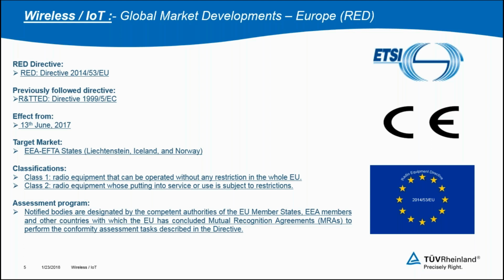Under each directive, usually there will be a list of harmonized standards which you need to show compliance with in full before you place the device into the market. In case there are any restrictions, especially where certain bands or certain power levels are not uniform within the European Union, in such countries you need to place the device with a restriction, or you would need to go to a so-called notified body, who would evaluate the product to specific country requirements, whether they have been taken care of or not. This is called a notified body CE marking, used when compliance to all European country requirements is not fulfilled. So this is how compliance to European standards would happen.